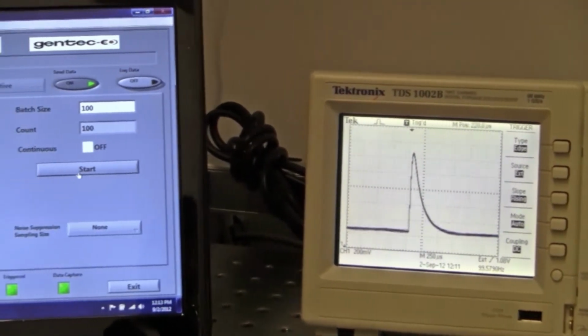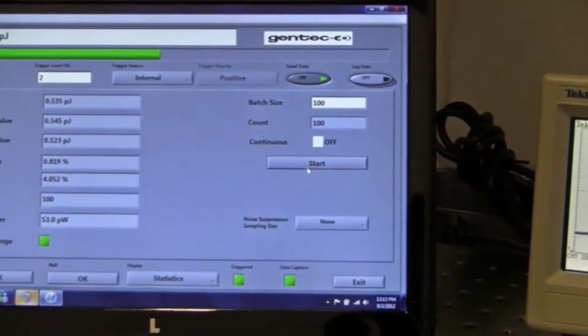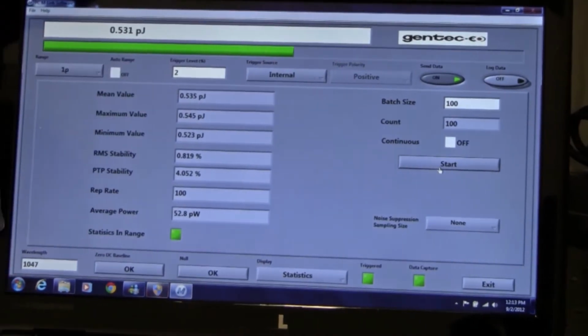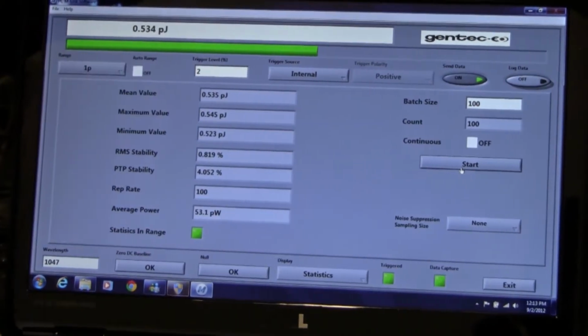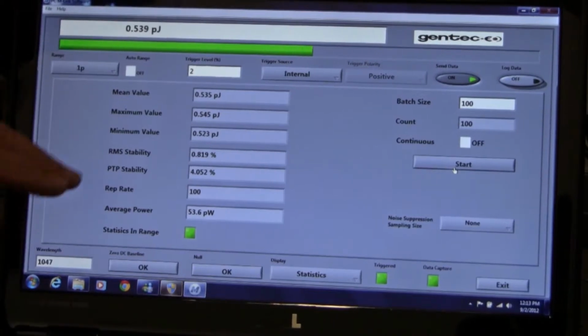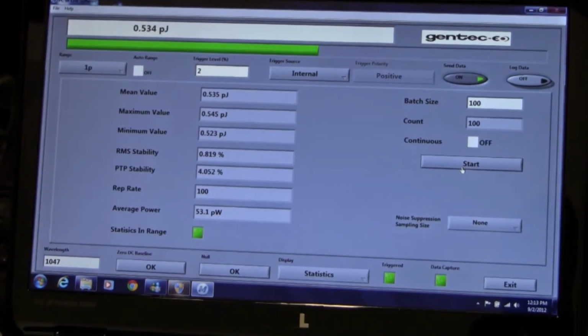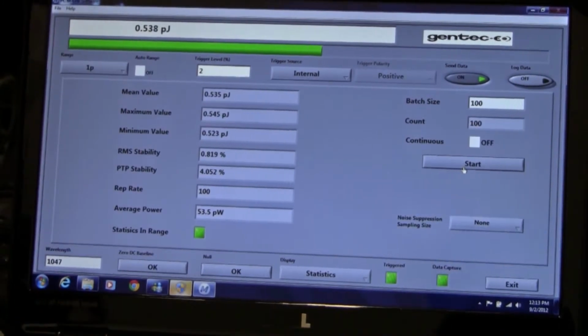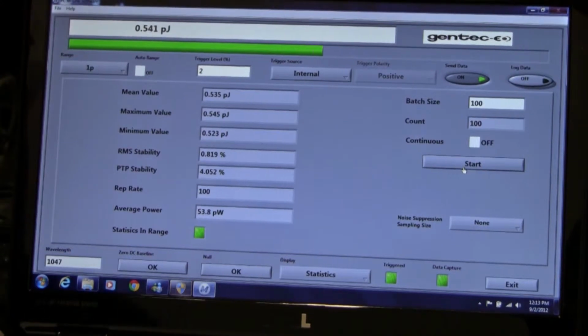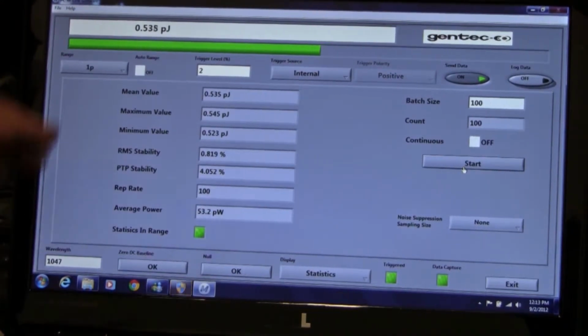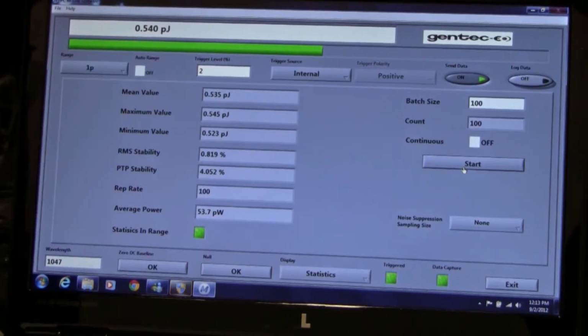We've got the instrument set up in the internal trigger mode, a 2% trigger level. We're reading about 535 femtojoules with an RMS stability of less than 1%. Now let's go back and attenuate the laser down to the 10 to 20 femtojoule range and look at this voltage output and the instrument software again.